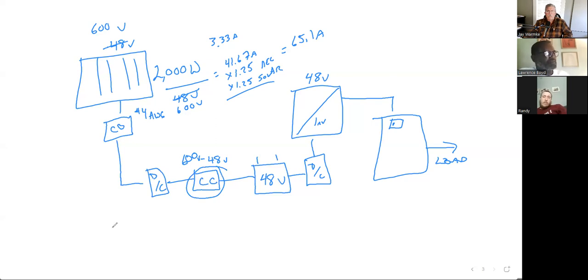You only have to do that before you get to the first piece of electronics that controls the system. In this case, the charge controller. From that point forward, the voltage is controlled by the charge controller, whether the sun's energy changes or not. If I've got a solar panel with a microinverter hooked right to it, all my wiring from that point forward doesn't need the second adjustment because the microinverter is controlling the system.